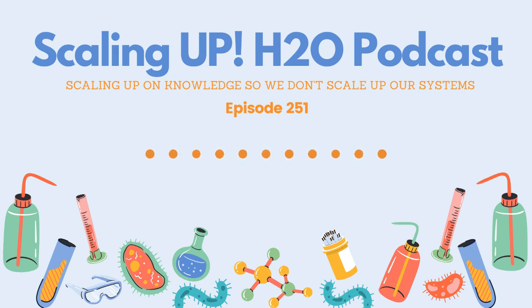And then also cleanliness. We make sure we clean our meters at least every week or as needed. If we have a dirty meter, and whatever we're testing has to transmit through that dirt into whatever the probe is, we're not going to get a good reading. And if we calibrate off of a dirty probe, well, folks, that's not a good calibration, because we're taking into account all the gunk that's on the probe, and we're doing really what's called a false calibration. So make sure all your meters are clean, they are calibrated, and just in case, I have things to clean my meter in my test kit, and I have all the standards so I can test for calibration or accuracy anytime throughout my day. I'm going to do the same thing with the probes on the controller if they are not reading what my meter says that they should be reading.